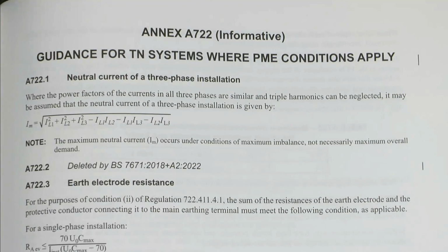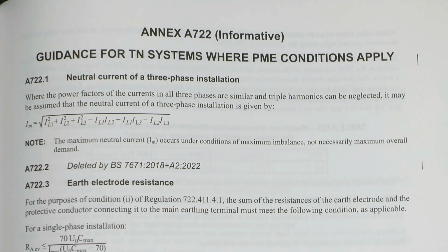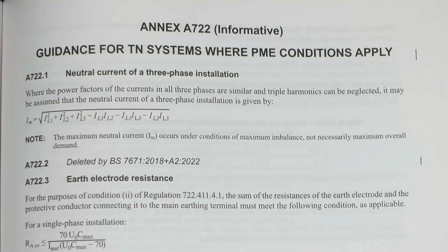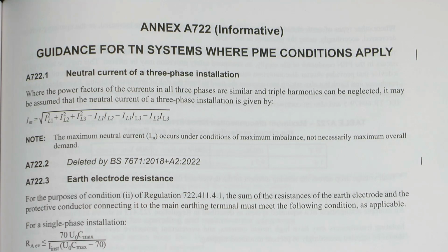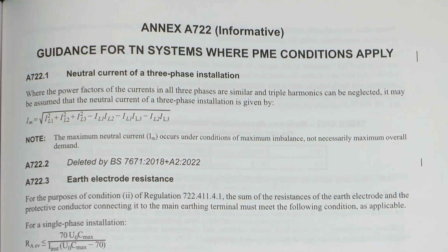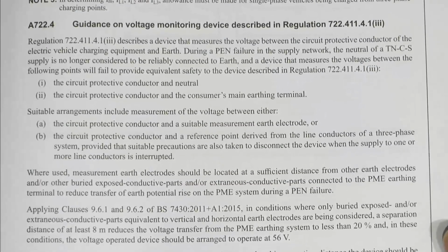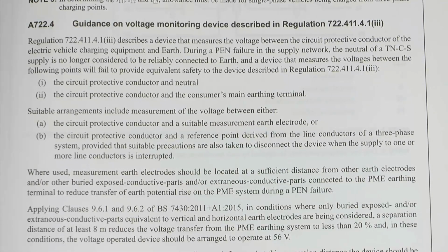Now, Annex A722, which is informative, it says there, it's not theoretically part of the regulations themselves. A few adjustments there. Deleted that part there because that's about the three-phase type of installation, which of course you can't use anymore, so of course that's been removed. And the other bit we've now got is this bit, A722.4, guidance on voltage monitoring device as described in regulation 722.411.4.1 indent 3.